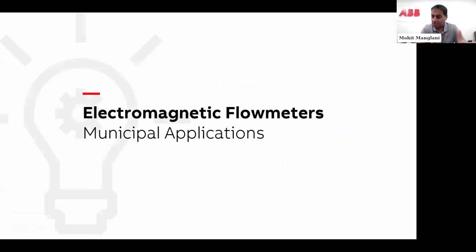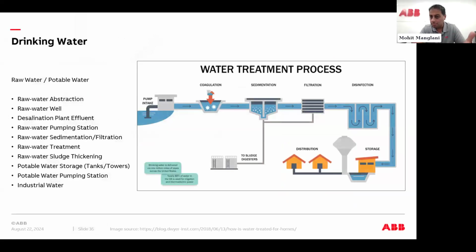So with that, that's mag meters in a nutshell. I hope I've covered the majority of what people are looking for. We're going to go into a little bit of an application side. In my market, obviously the water market, mag meters are used in almost every step of the process, because before something goes into a process and after something comes out of a process, you need indication of what's happened to the flow, whether you're dosing, whether you're using a totalized value, whether you're putting it into storage so you know how much you have in your tank or vessel, whether you're using it in potable water distribution or wholesale potable water management. You need to know what's going through your line. And you need to either bill accordingly, or make sure that water is not being lost or leaked somewhere. The idea is that this is where mag meters spend their best times.